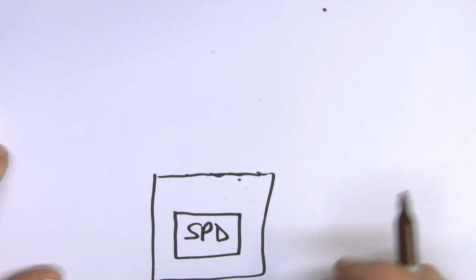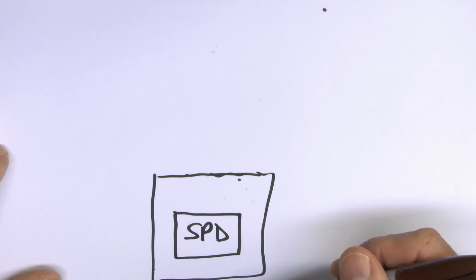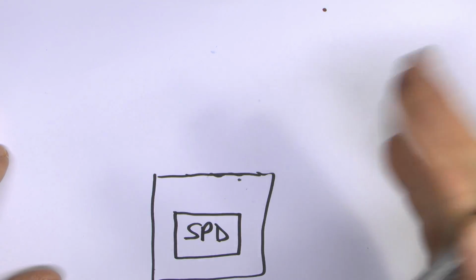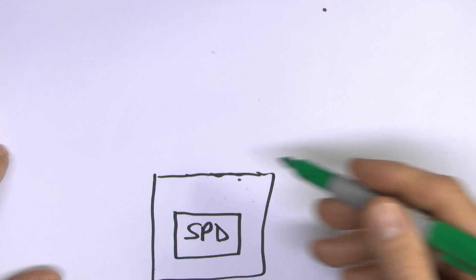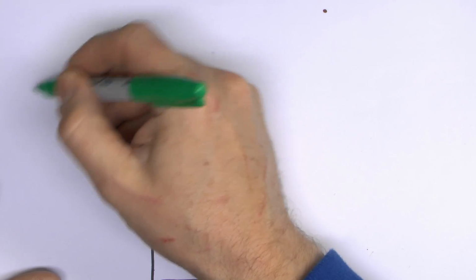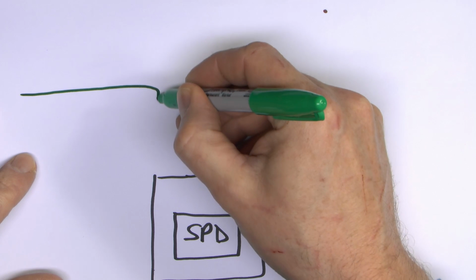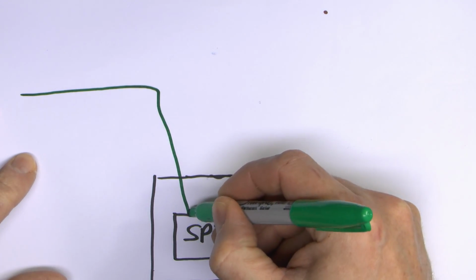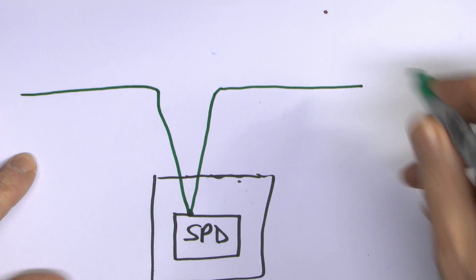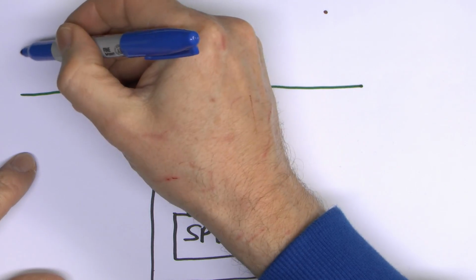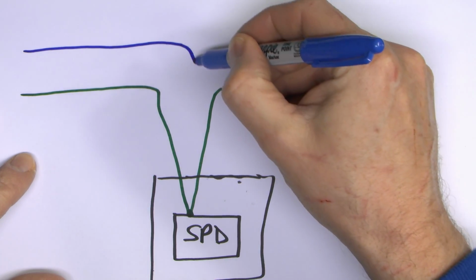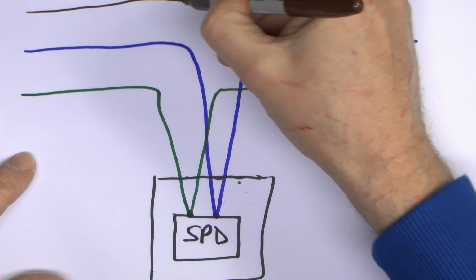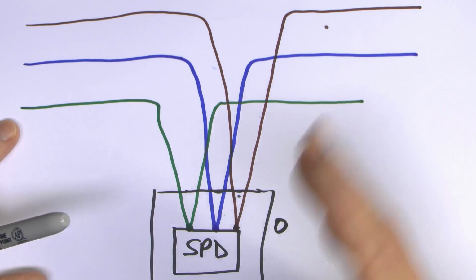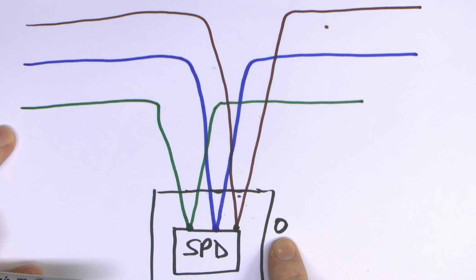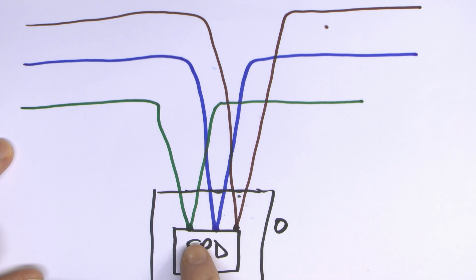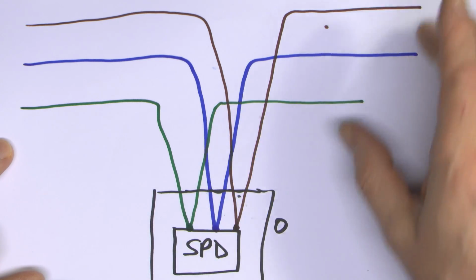Now if you absolutely must do it in that fashion, in other words you're going to have the surge protector device in a separate enclosure with a set of terminals on the top, then there is a much better way of doing it, and that's to do it like this. So let's have the protective conductor coming along, and it will come across to the device here, and then it would come back out and continue to the installation. And it's the same with the other conductors, so I'll bring the neutral across here, and also the line in the same arrangement. Now in this case this is far better, and the distance here is effectively 0, because all the wires are coming to the surge protector device and then going back and connecting to the installation over there.